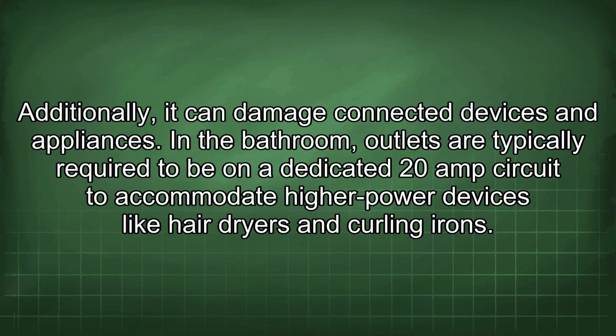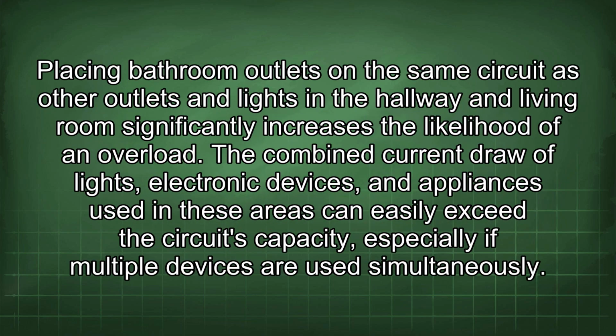In the bathroom, outlets are typically required to be on a dedicated 20 amp circuit to accommodate higher power devices like hair dryers and curling irons. Placing bathroom outlets on the same circuit as other outlets and lights in the hallway and living room significantly increases the likelihood of an overload. The combined current draw of lights, electronic devices, and appliances used in these areas can easily exceed the circuit's capacity, especially if multiple devices are used simultaneously.